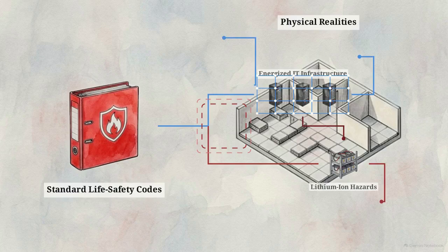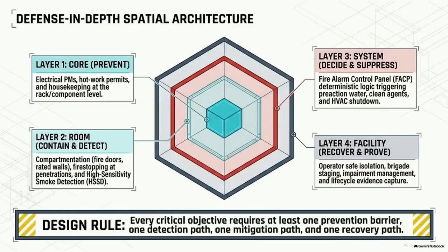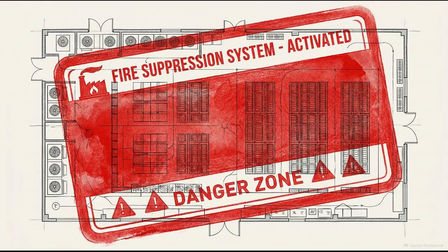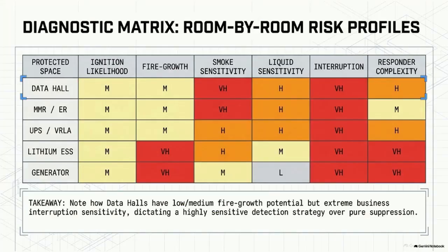of energized IT infrastructure. That bridge is built on a spatial architecture called defense in depth, designed to eliminate single points of failure. Every critical objective requires at least one layer of prevention, detection, mitigation, and a planned recovery path. Applying generic fire codes across a whole building ignores the unique hazards of specific IT zones. The diagnostic matrix for a standard data hall reveals a challenge. They have medium fire growth potential, but very high sensitivity to smoke and interruption.